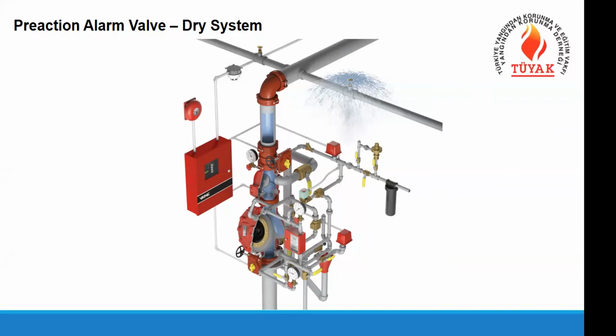It is in general also used in cold storage rooms that require dry systems. The pipes are filled with pressurized air, and we don't have water inside the pipes. Just to protect the room, we are protecting the devices or material inside from accidental water discharge. So this is kind of a double safety system when you consider very special and expensive room materials.